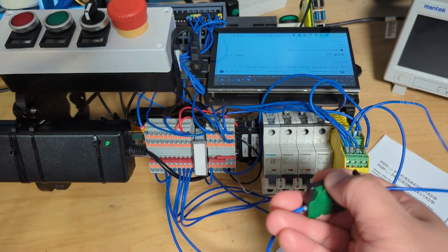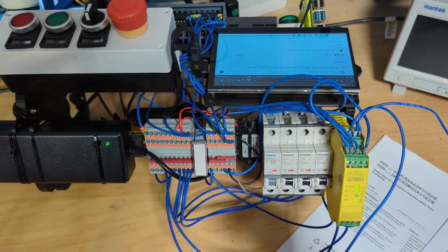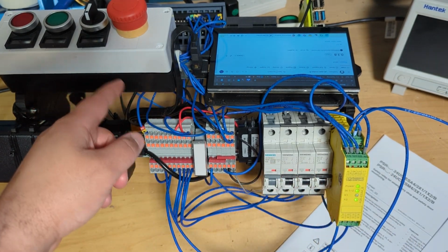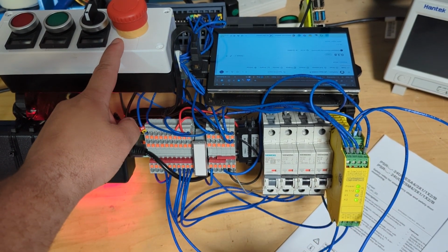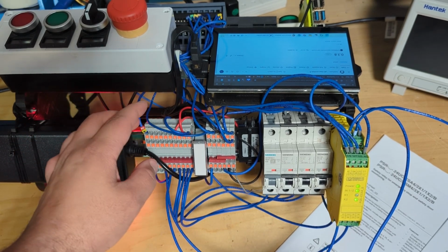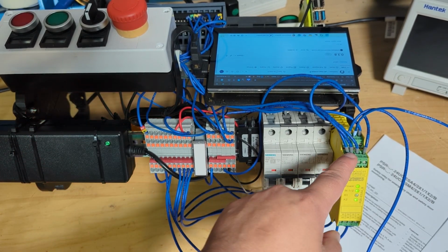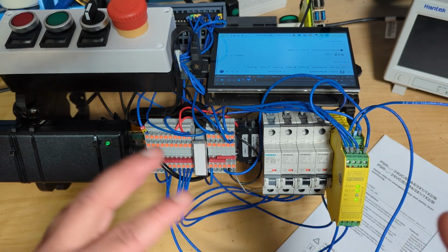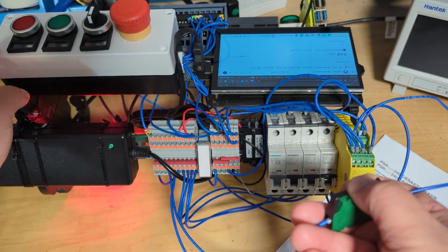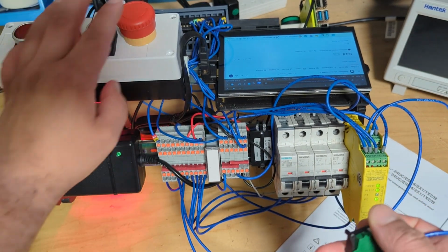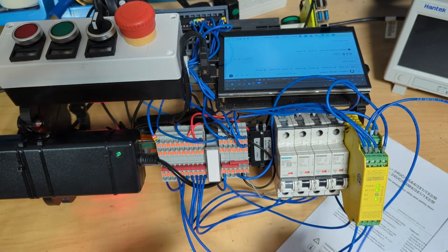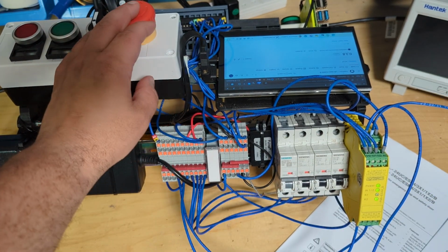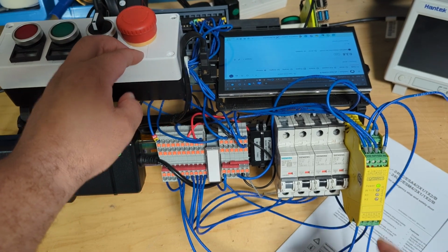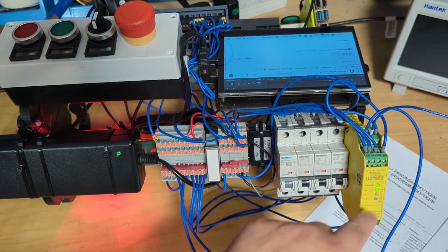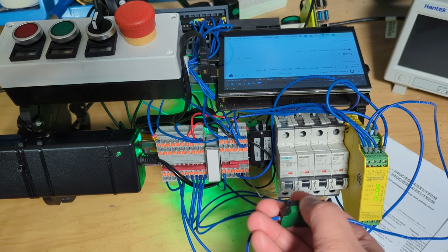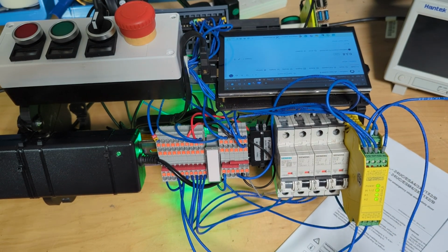I'm pressing my reset button and it's not working, because it's like, well, I've had a problem on that channel. Do you want to just hit the e-stop and reset it both? It's lost one channel, so why did we lose one channel and not the other? It's waiting now for me to reset it properly by hitting the e-stop, resetting it, then resetting again. Then it will go, okay, fine, I'll turn on my contact. So I hit the e-stop, I lose everything, reset it, I get my inputs back, then reset, boom. It's really nice, isn't it?